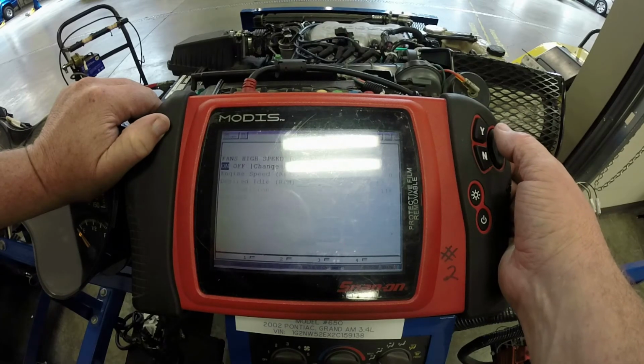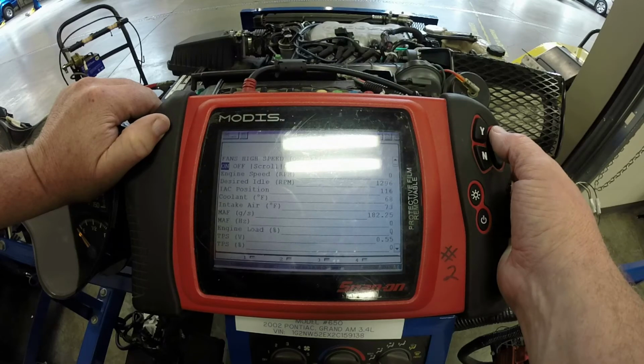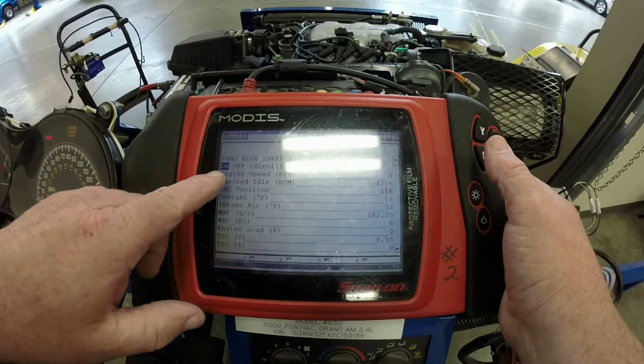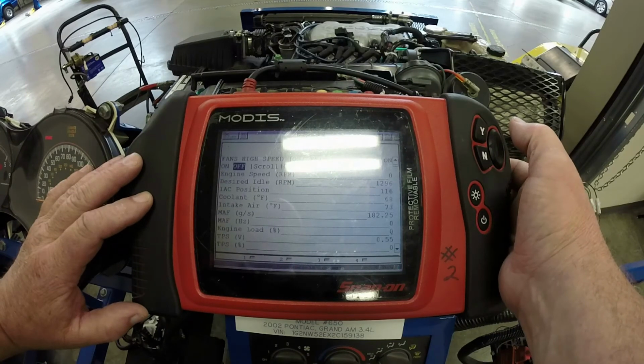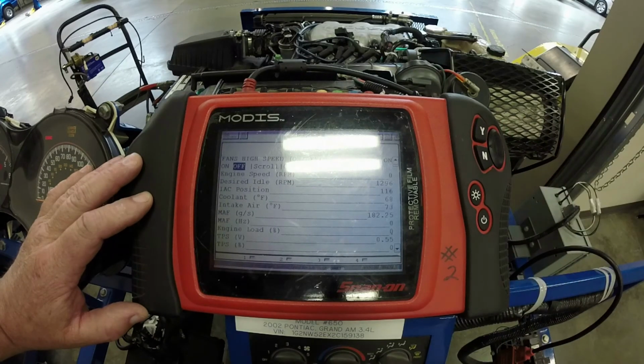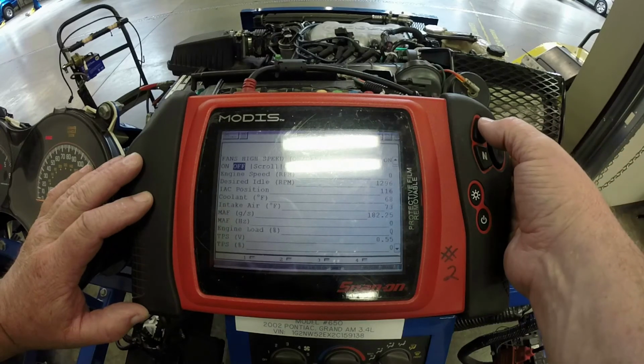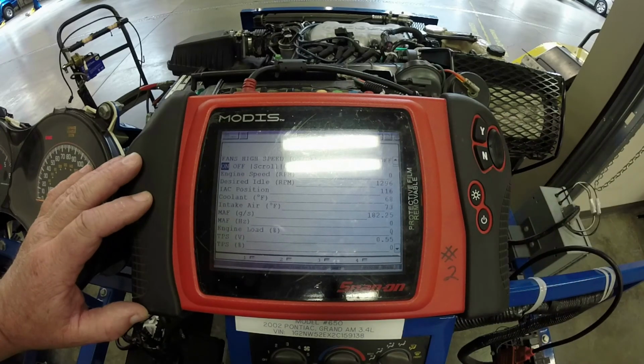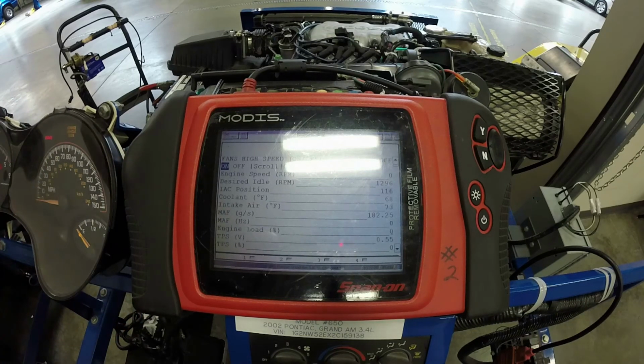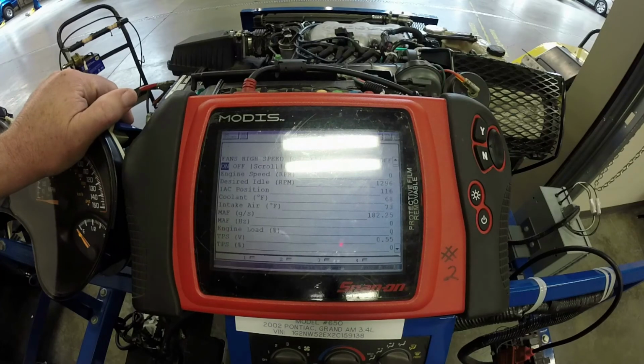I'm going to click on it since it's highlighted. As you can hear, the cooling fans kicked on. Now I'll turn them off, and the cooling fans go off. That tells me the high speed cooling fans work, both of them. So if my cooling fans give me a problem, I know it's not the fans, because they work. It might be an electrical issue.